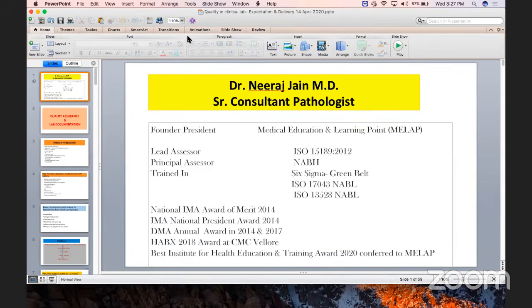You have controls for only, suppose, 15 days. Otherwise also, to see whether you are storing samples properly or not, you test some stored sample. So how much difference you are getting? Suppose for hemoglobin, in the morning it was 13.2 and in the evening it is 13.4, or next day it is 13.4. Difference is 0.2. Similarly, a sample tested tomorrow, you are testing again day after tomorrow. Suppose for hemoglobin difference is 0.3. Someday difference is 0.1. That way you collect 30 data points.